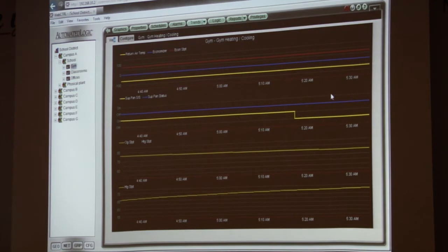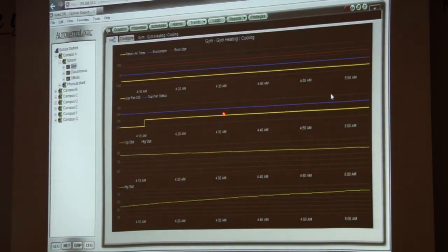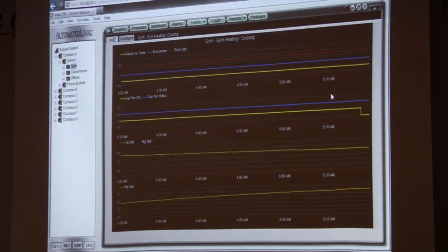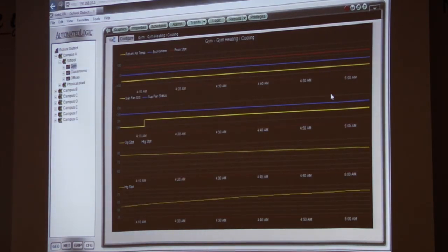See, I can see over here where it turned off, and I can see here where it turned on, right? So now that's about as close as I could get where I could kind of keep track of it. Now I can see that my heating set point, right, when it went on, all during that time, from 4:10 to 5 o'clock, so for 50 minutes, that temperature started to go up, right? So you could use your keys to zoom in on your problem.